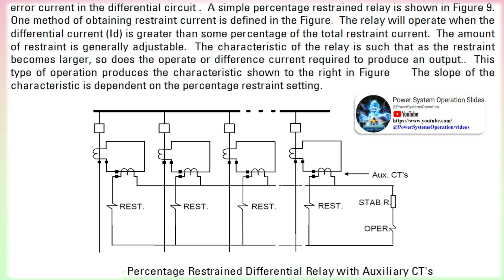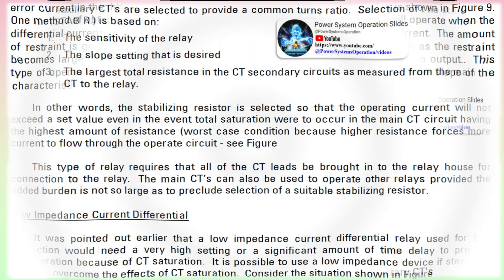One advantage to using this type of relay is that the junction point of all of the CTs can be — and should be — made in the yard rather than in the station house. Location of the junction point in the yard minimizes the amount of wiring required and in turn leads to lower settings and thus more sensitive protection.